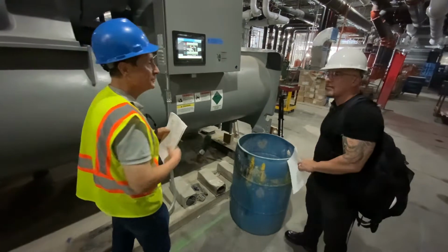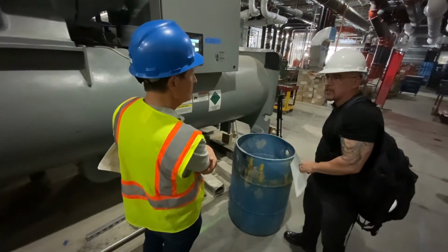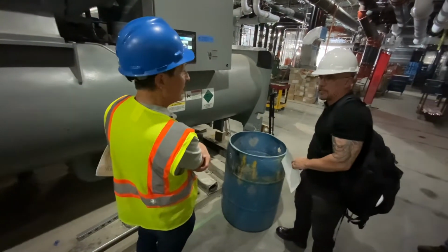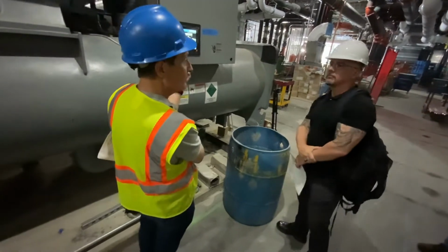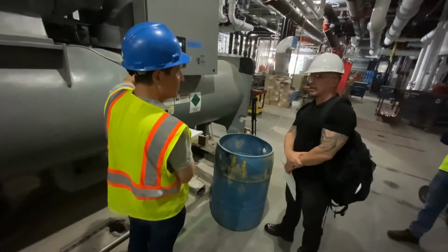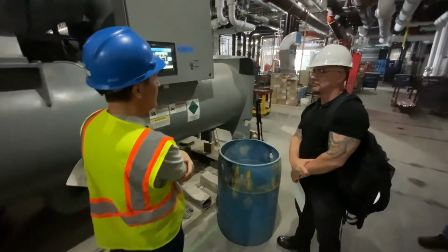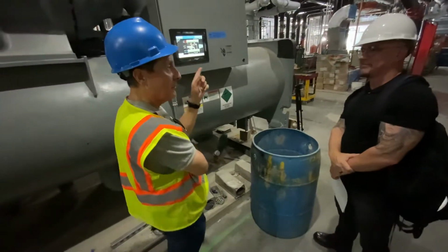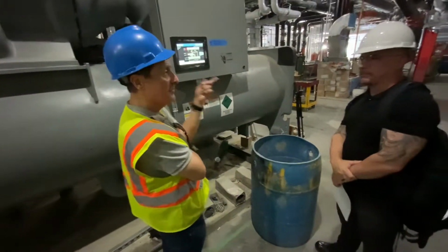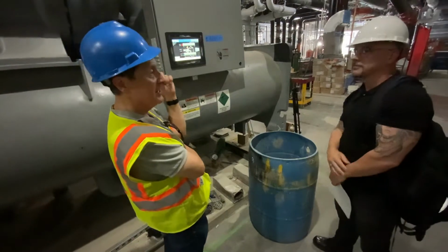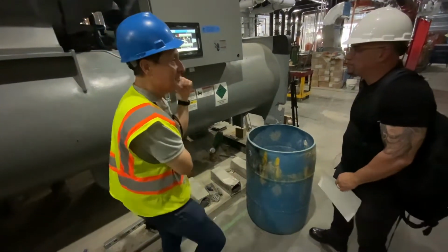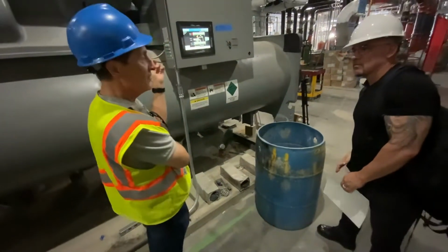From an efficiency standpoint, is it better to run your cooling tower water a little bit lower? Absolutely, yeah. Because this machine will run more efficient because the speed of the compressor will slow down. You will consume more brake horsepower of your tower fans, but they're smaller fans. This is a bigger motor. This is the biggest energy sucking device in the building. So we try to focus on him first, everybody else secondary.